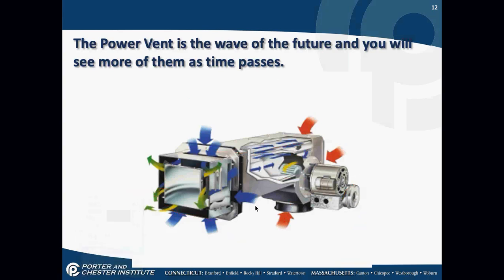Okay, so if you replace this part, while you're at it, you may end up replacing the motor because the shaft is so damaged you might not get a new squirrel cage on it. Okay? So parts are replaceable, but sooner or later the entire metal housing is going to start wearing down. And at that point, you just can't replace pieces of metal housing. It's done. All right. Any other questions on power venters? So if I came along and asked everybody the sequence of operation for an oil burner with a power venter, everyone would be able to tell me what it is? Not immediately.